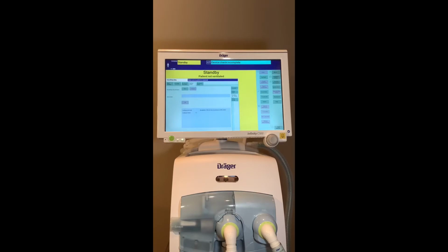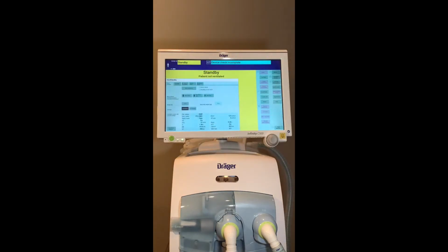Once the device check has been completed and all the components have passed, the user will be prompted to continue to the breathing circuit check. This process is done the same way, by pressing the start button and confirming by pressing the rotary knob. The user will then answer the questions on the screen as well.